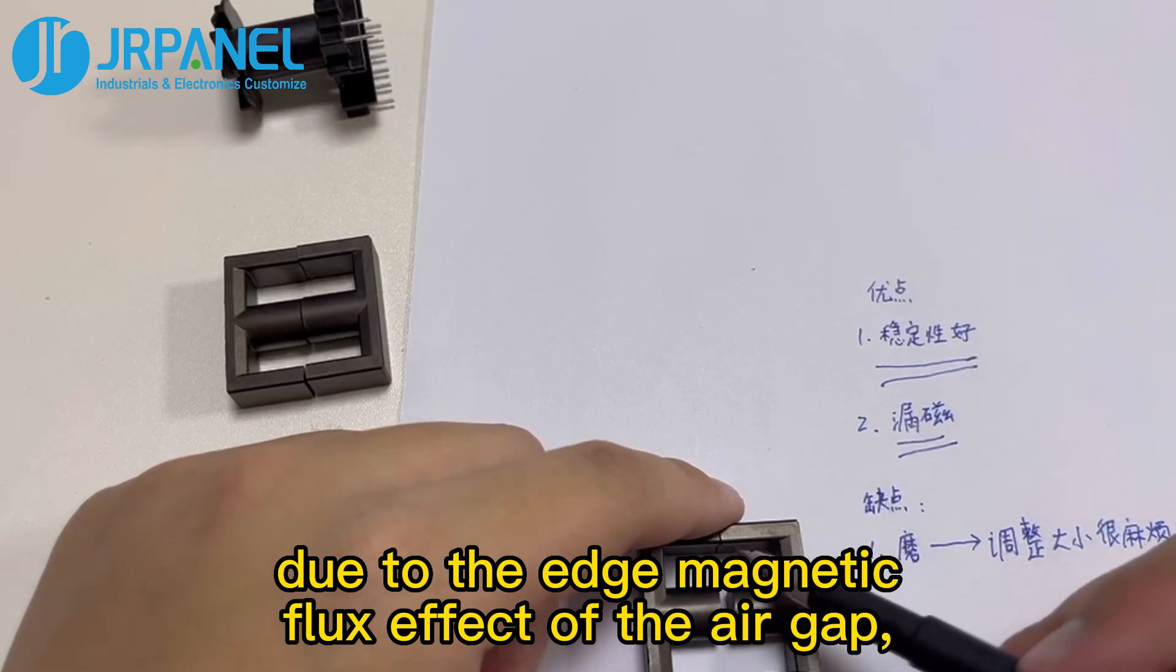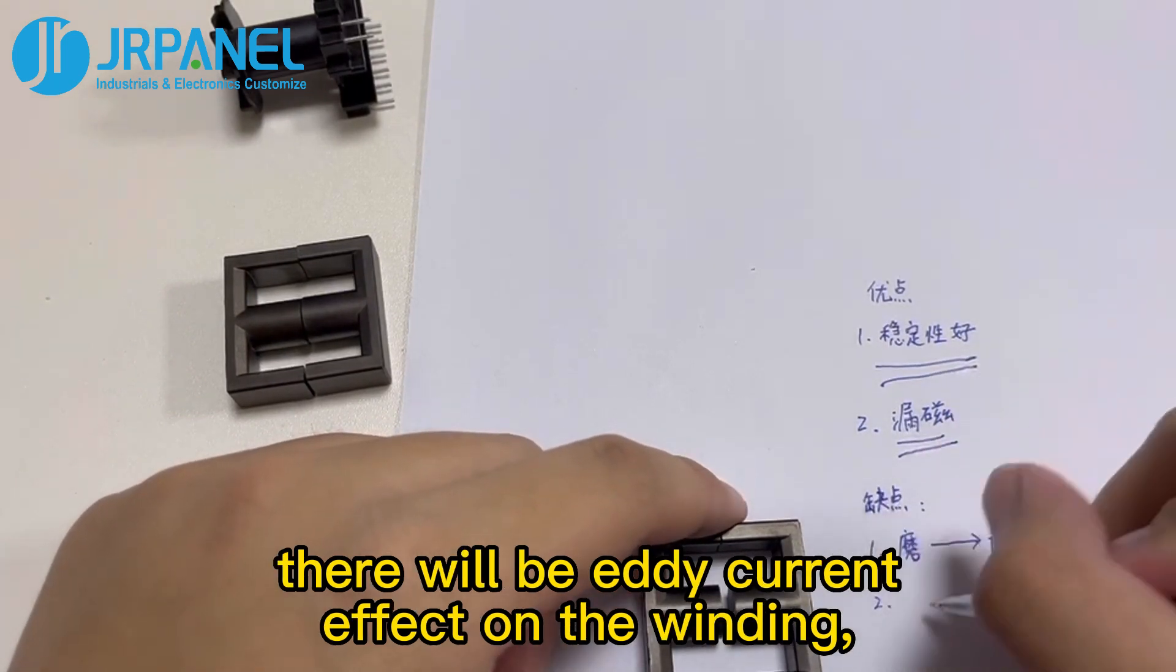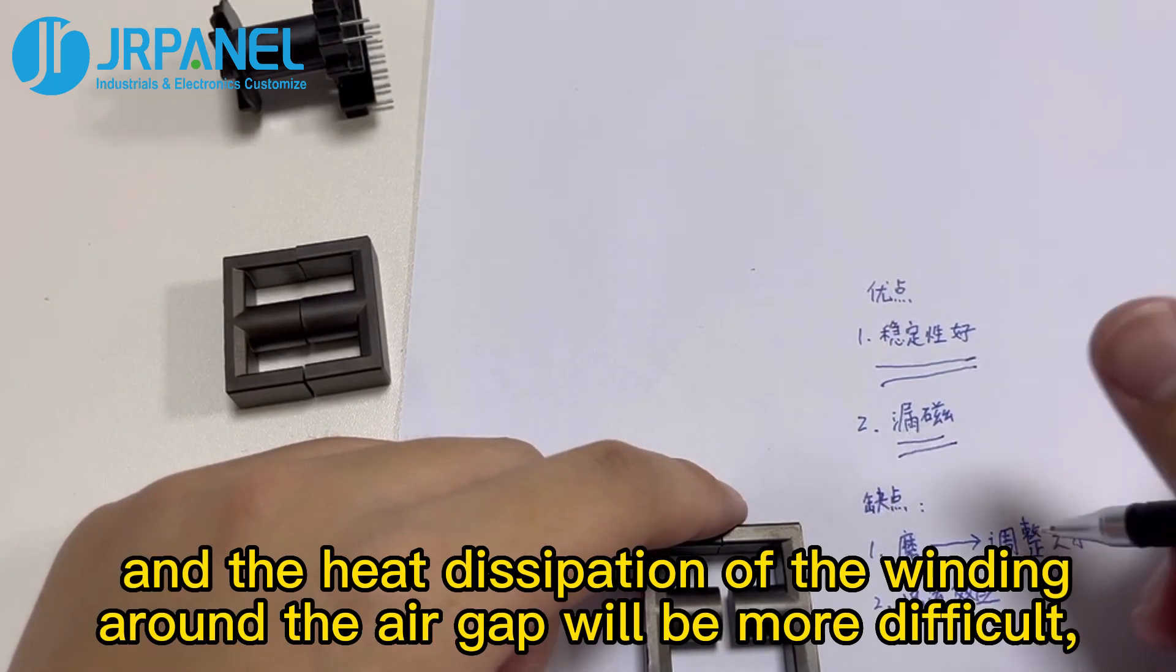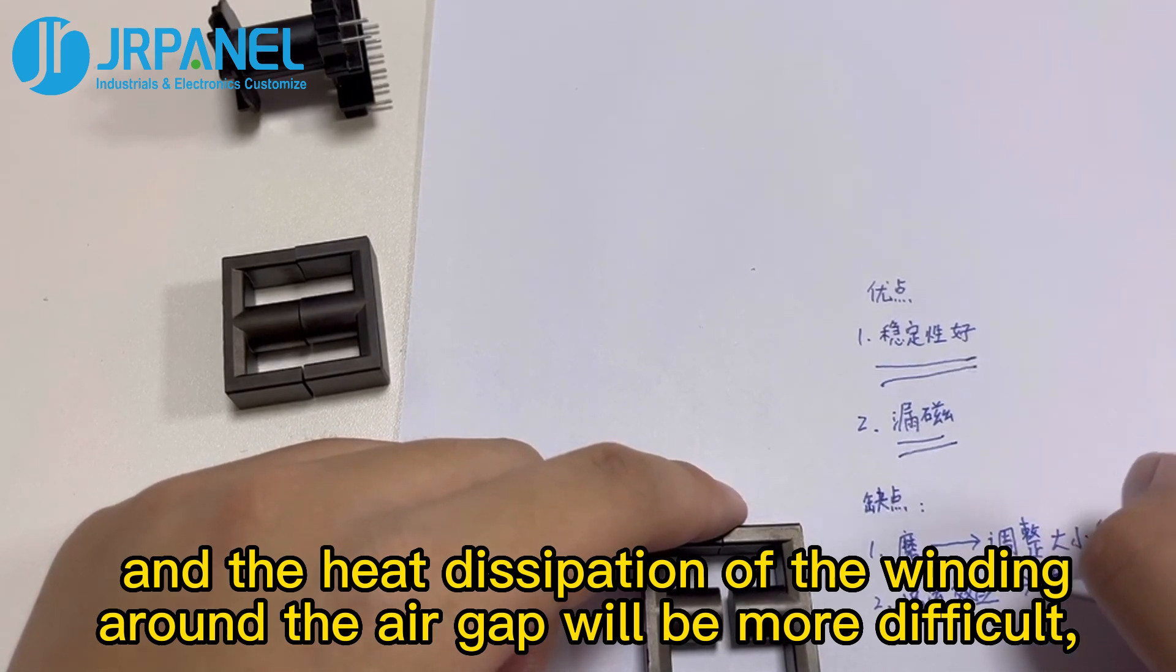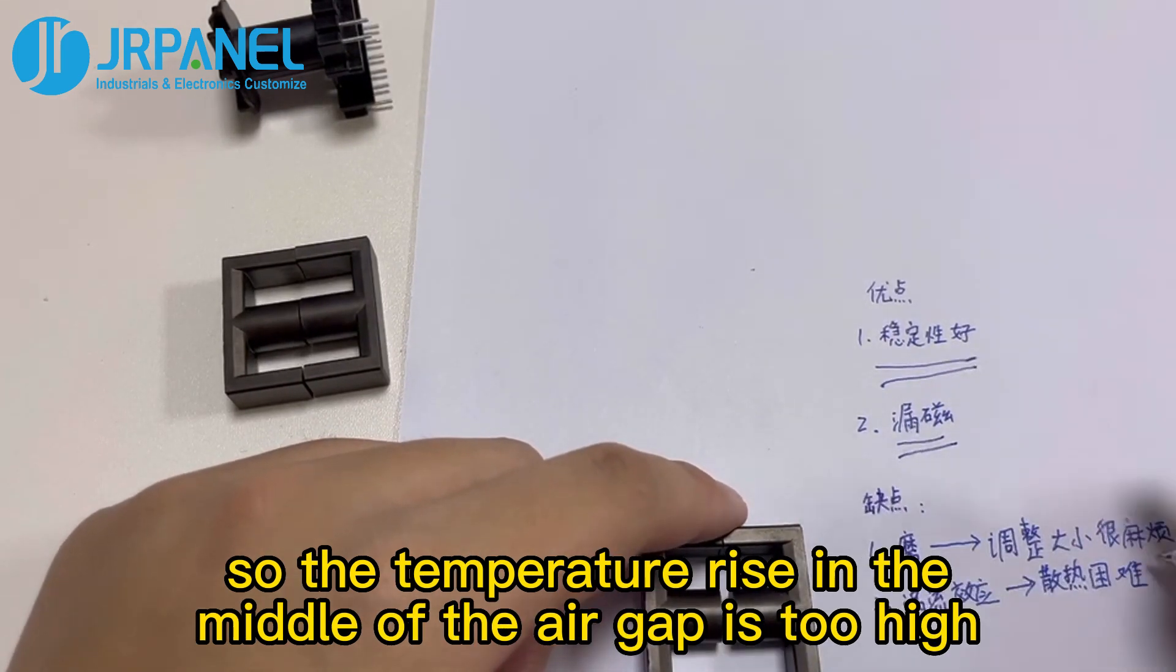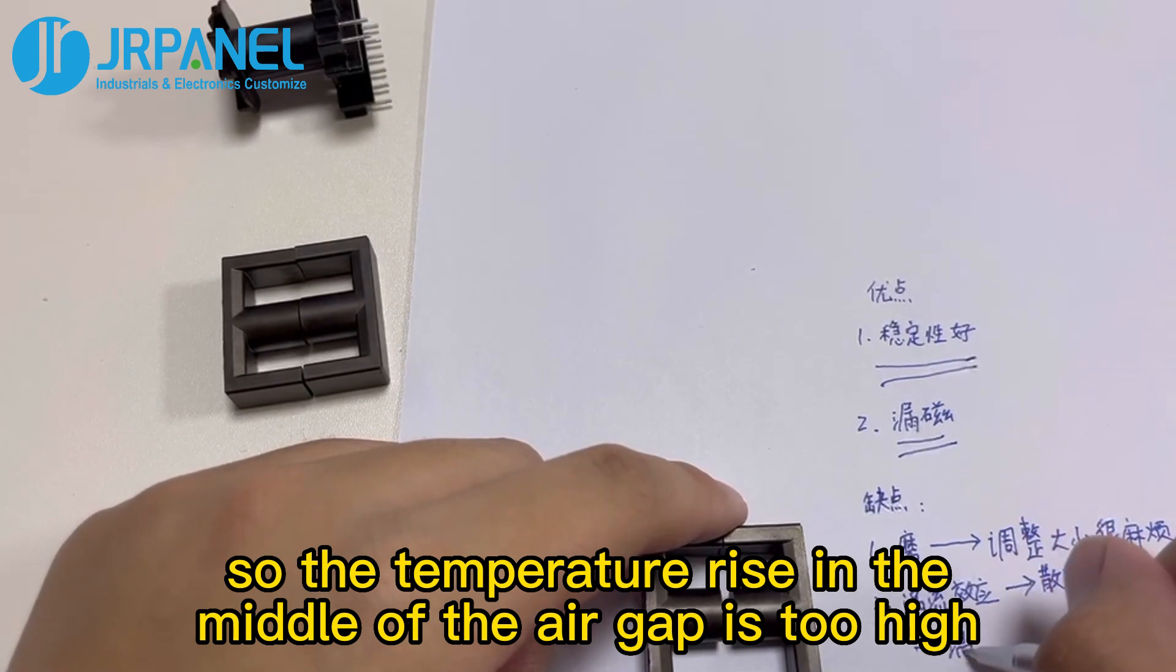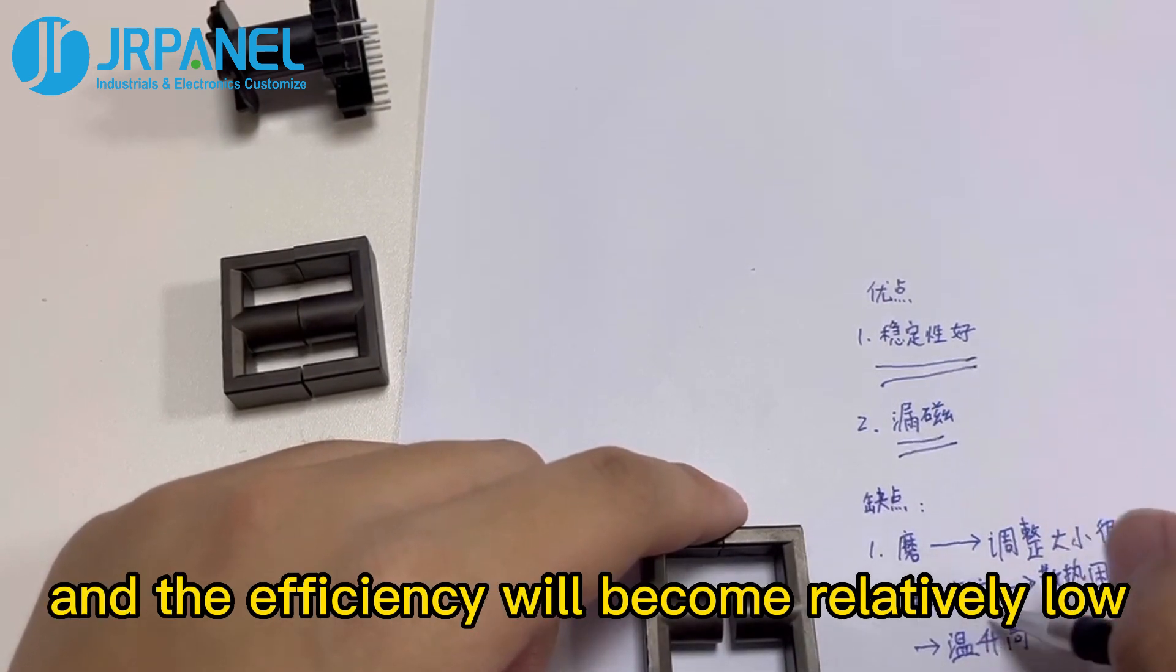In addition, due to the edge magnetic flux effect of the air gap, there will be eddy current effect on the winding. And the heat dissipation of the winding around the air gap will be more difficult. So the temperature rise in the middle of the air gap is too high, and the efficiency will become relatively low.